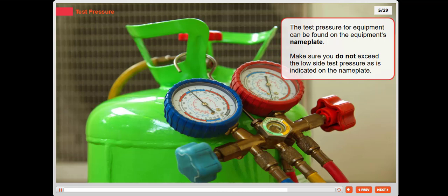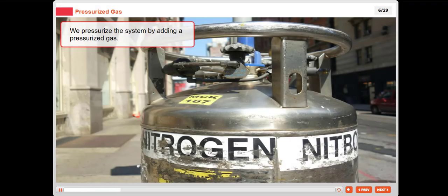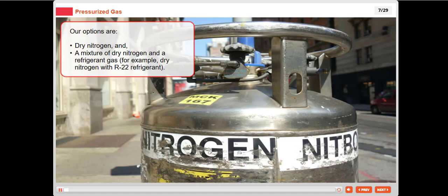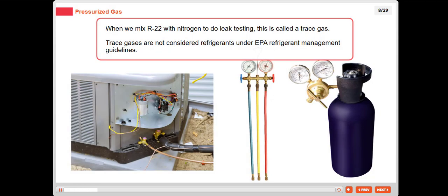We pressurize the system by adding a pressurized gas. Our options are dry nitrogen and a mixture of dry nitrogen and a refrigerant gas, for example, dry nitrogen with R22 refrigerant. When we mix R22 with nitrogen to do leak testing, this is called a trace gas. Trace gases are not considered refrigerants under EPA refrigerant management guidelines.